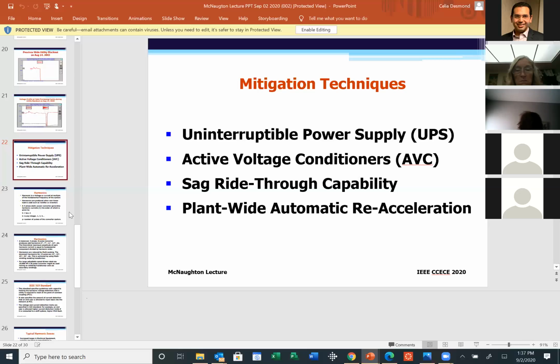The other option, which I have personally implemented, we call sag ride-through capability. If you have an important piece of equipment in your plant, like a large variable frequency drive that is driving a critical process, a large compressor or pump, and when this electronic device experiences a voltage sag, its control has enough power in it that it keeps the control healthy, so that when the voltage is restored to its normal value, the control has the smarts to know where the motor speed dropped to and bring it back up to what we call the pre-disturbance speed. This one is a very, very specific application, and to my best knowledge, is mostly used in a process environment.